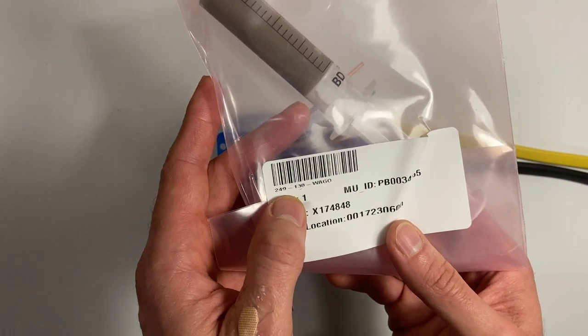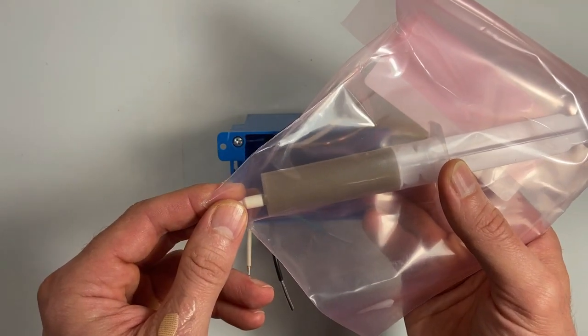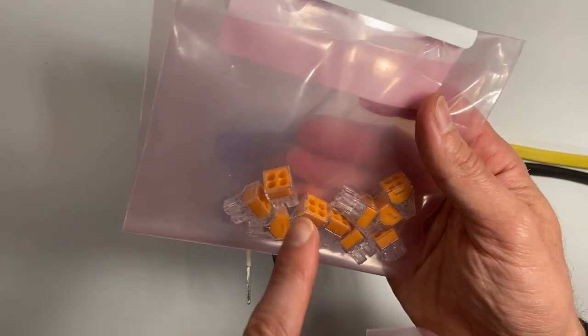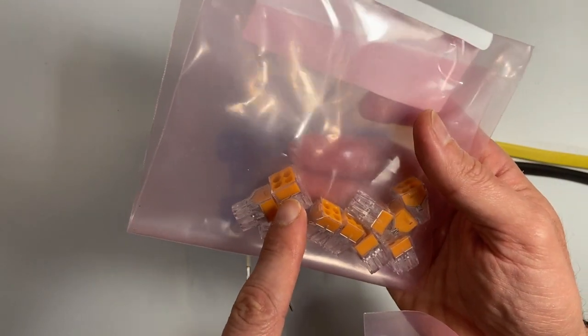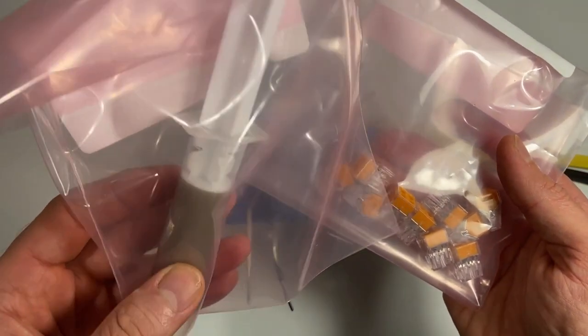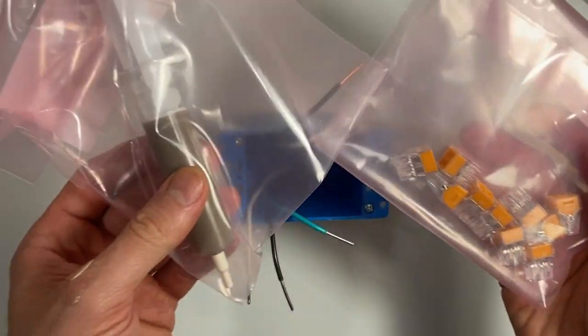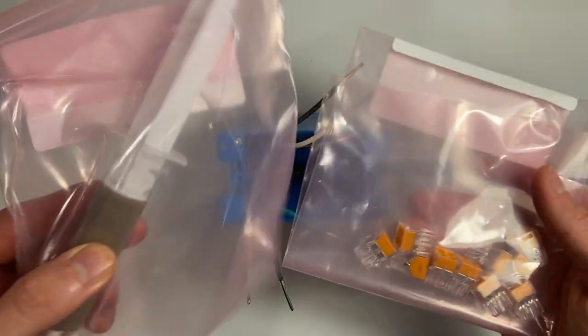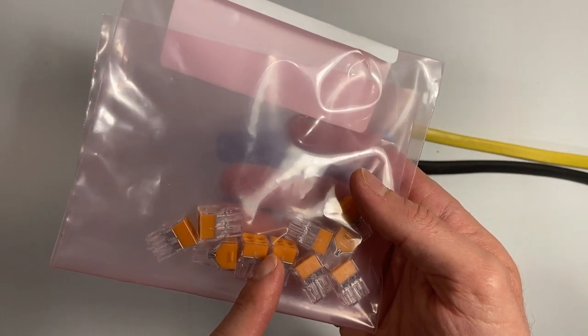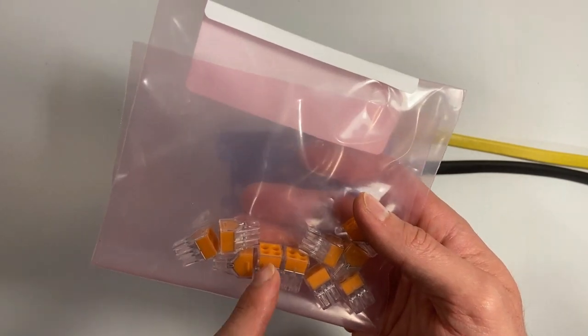But in that case you have to use their own paste. It's called Alu-Plus, also made by Wago. That's their part number. It's not expensive, you can pick one of these syringes up for around five dollars. And these are available all over the place. There are look-alikes, Ideal makes similar looking ones, but for use on aluminum with this paste make sure you're picking up the authentic Wago ones and use their own paste.